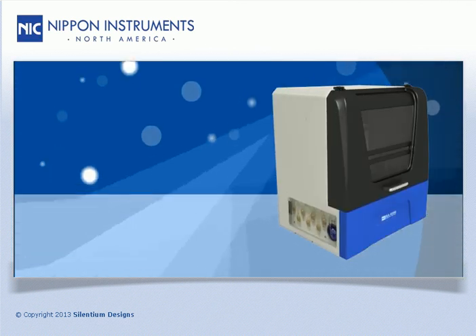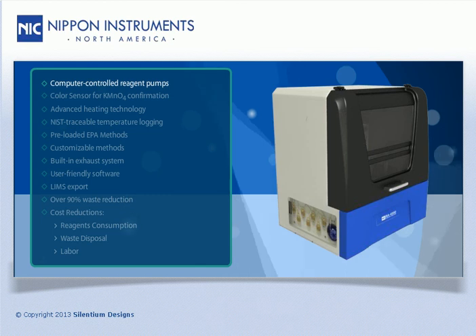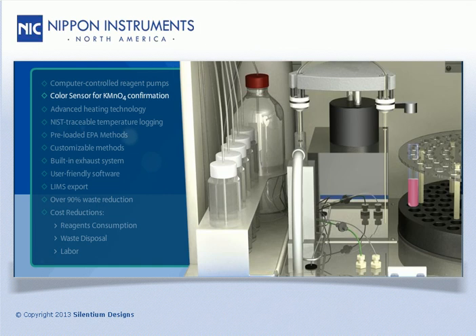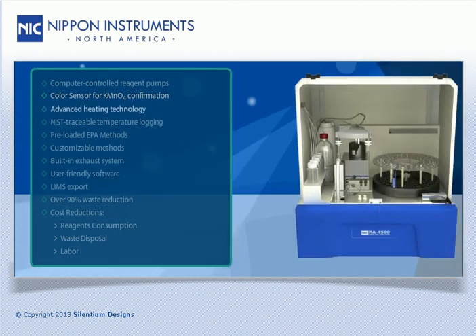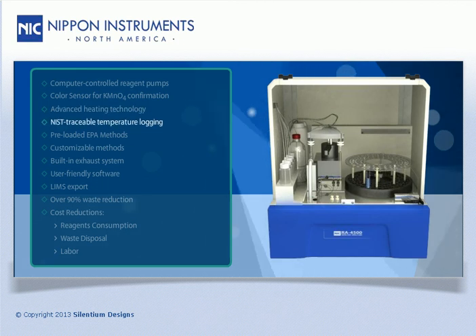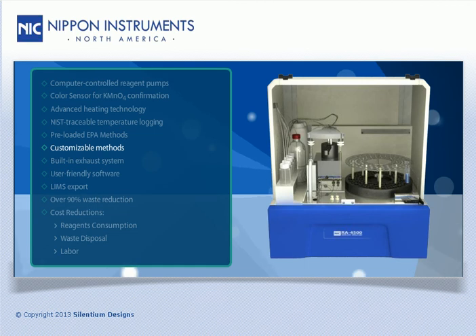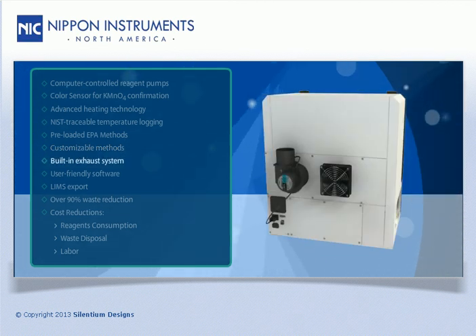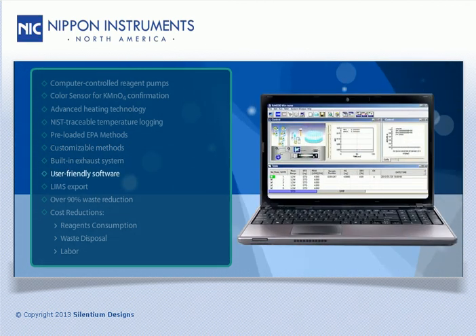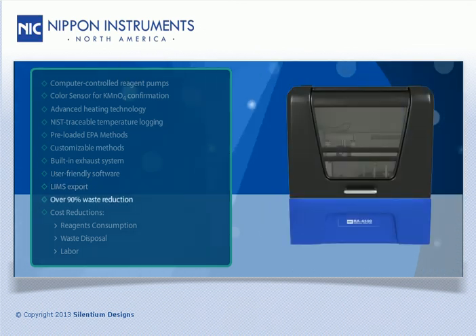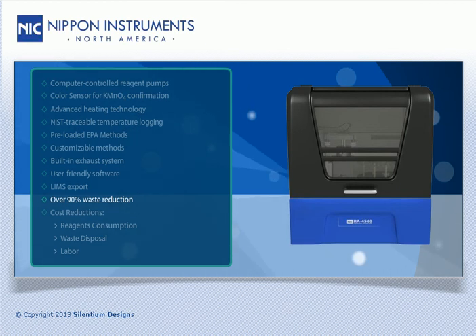The RA4500 features computer-controlled reagent injection pumps for accurate and precise reagent addition, a color sensor to ensure the presence of excess potassium permanganate, advanced heating technology, NIST traceable digestion temperature logging, pre-loaded and customizable methods that include sample digestion and analysis, a built-in exhaust system, user-friendly software with LIMS export function, and over 90% reduction in generated waste versus traditional techniques.